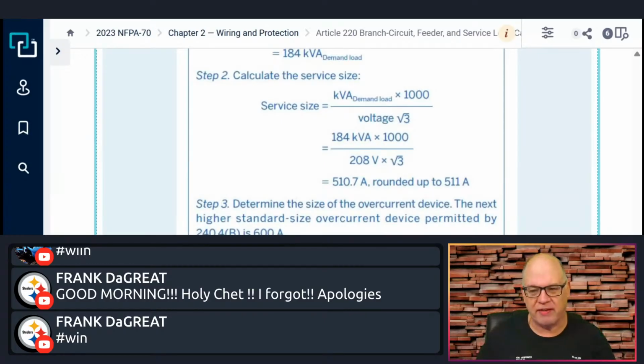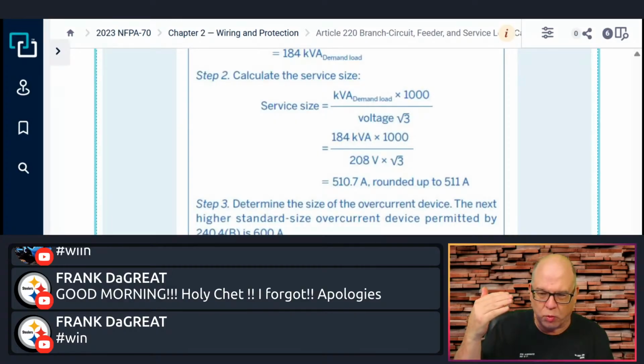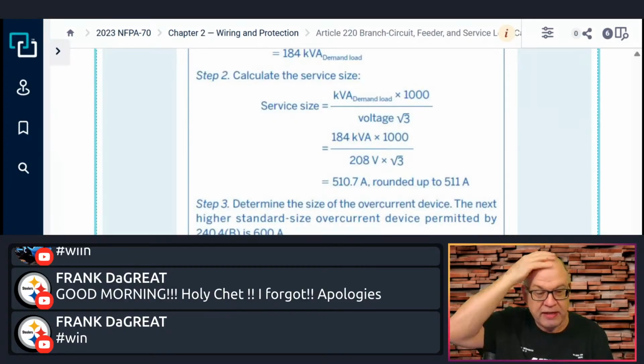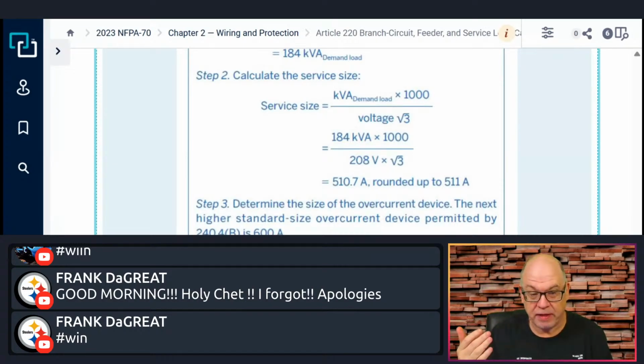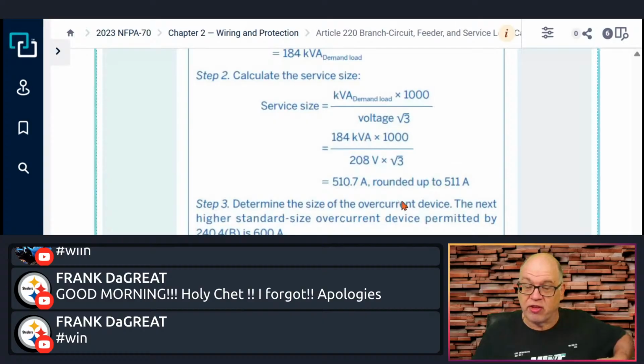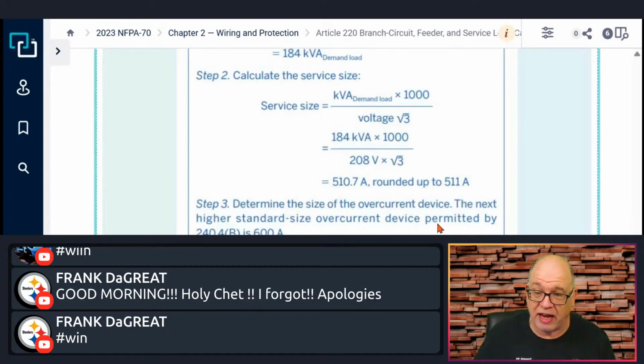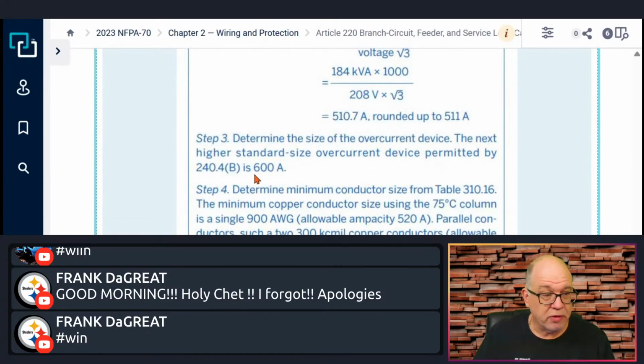Okay, so you remember what it says in 240.4(B)? As long as it's not over 800 amps. If it's over 800 amps, then the next size up doesn't work. So if it is not over 800 amps, then we're allowed to use 240.4(B), and we can go to the next standard size overcurrent device. The standard overcurrent devices are listed in 240.6(A). There's a little table there. You with me? All right. So in this case, there isn't an overcurrent device that's rated for 511 amps. So the next standard size is 600. So that's why you can have a 600 amp overcurrent device.